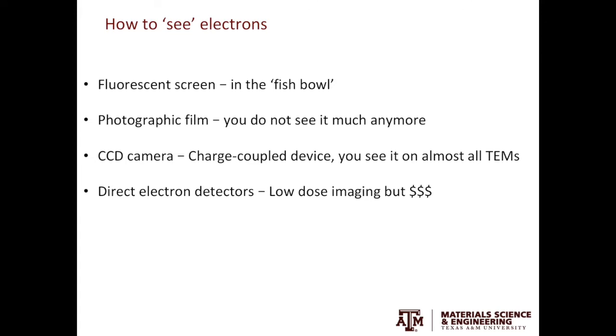The first type is the fluorescent screen in the viewing chamber, also called the fishbowl. You can also record images and diffraction patterns on photographic films, which you don't see much nowadays. The third type is the CCD camera — CCD stands for charge-coupled device — and nearly all TEMs nowadays are equipped with CCD cameras. The last type is the direct electron detectors, which are super expensive but ideal for low-dose imaging.